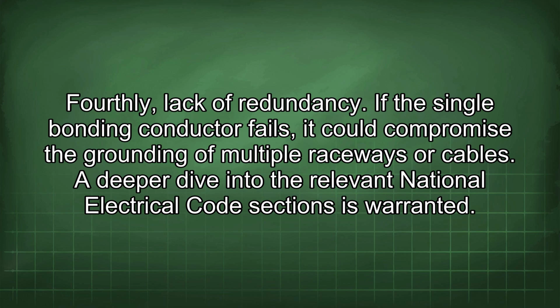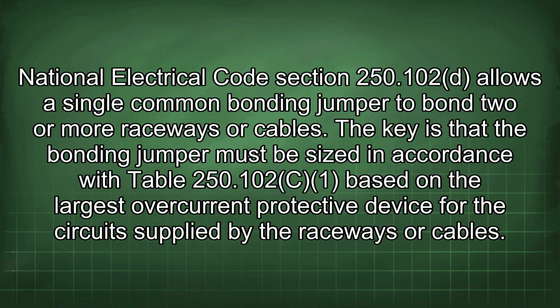A deeper dive into the relevant National Electrical Code sections is warranted. National Electrical Code Section 250.102 allows a single common bonding jumper to bond two or more raceways or cables. The key is that the bonding jumper must be sized in accordance with Table 250.102(C)(1), based on the largest overcurrent protective device for the circuit supplied by the raceways or cables.